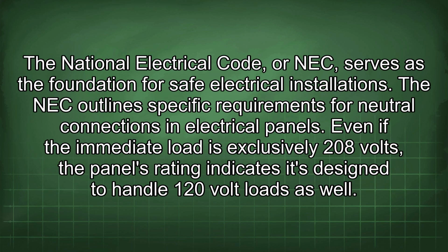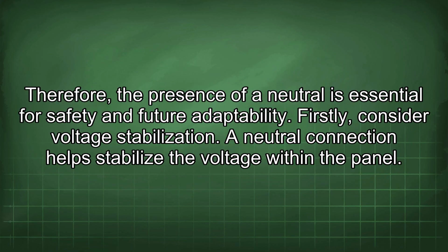The National Electrical Code, or NEC, serves as the foundation for safe electrical installations. The NEC outlines specific requirements for neutral connections in electrical panels. Even if the immediate load is exclusively 208 volts, the panel's rating indicates it's designed to handle 120 volt loads as well. Therefore, the presence of a neutral is essential for safety and future adaptability.